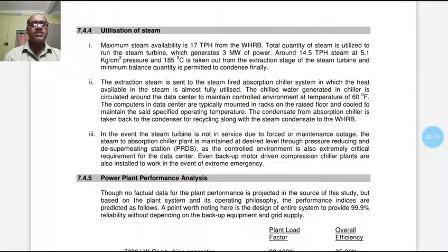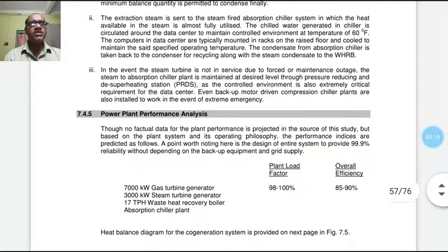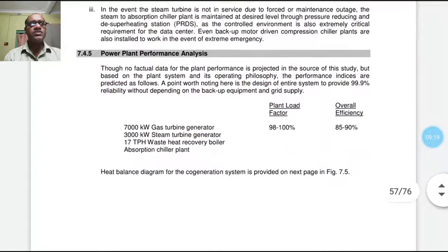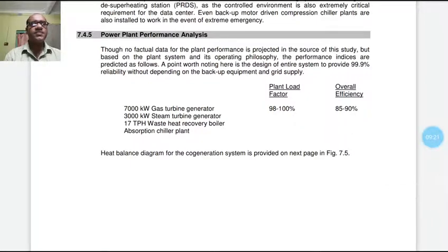Power plant performance analysis. Though no factual data of the plant is projected in the source of the study, based on the plant system and its operating philosophy, the performance indicators are predicted as follows. The point worth noting here is the design of the entire system to provide 99.9% reliability without depending on backup equipment and grid supply. So the plant load factor overall is 98 to 100% and overall efficiency is 85 to 90%.